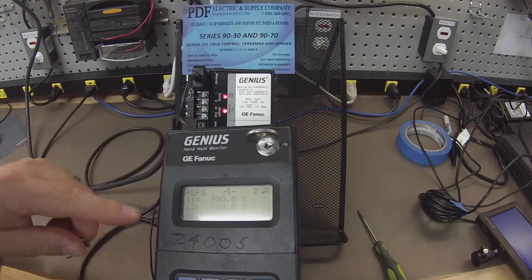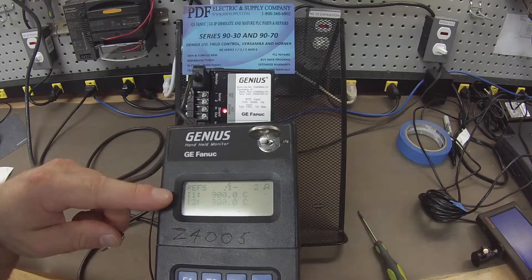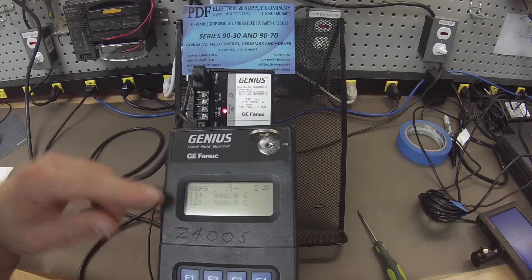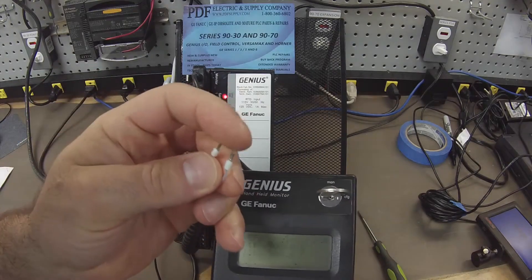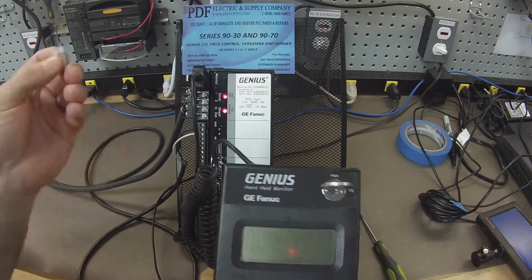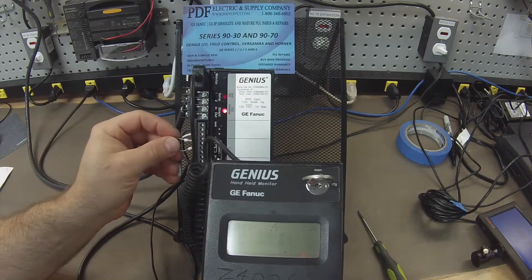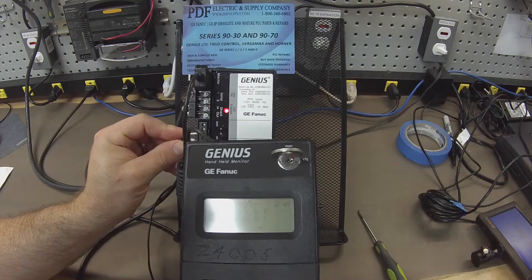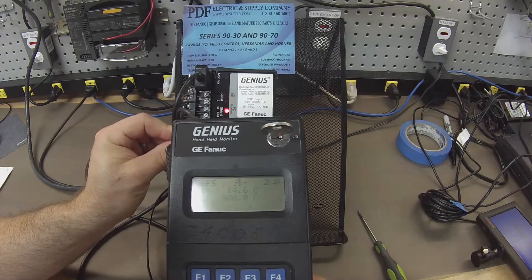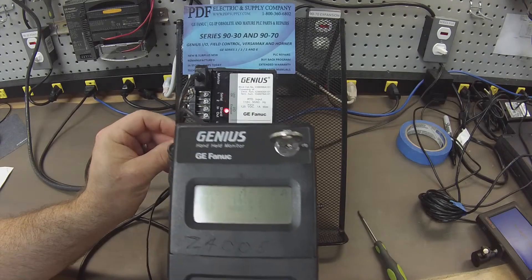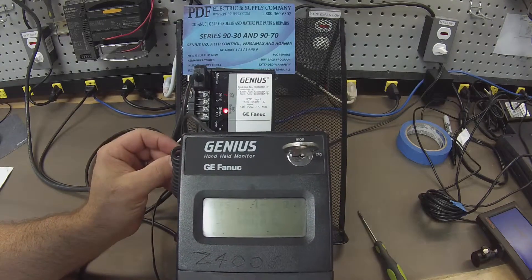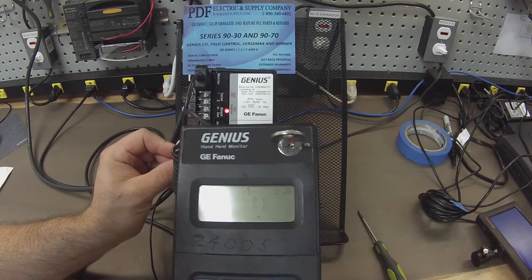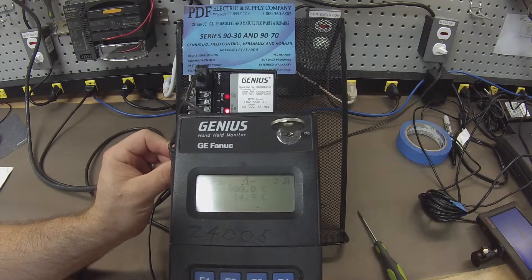And I'll let you know what terminals I'm using in order to get these figures. Now all the channels have been configured the same. So I'm expecting very, very close to the same result for each channel once they're probed with the two ends, these two leads off of my resistor. So channel number one. I'm probing terminals 9 and 10. I'm getting a reading of 14.6 so pretty close to 15. Channel number two is terminals 13 and 14. 14.9. Again, very close to 15.